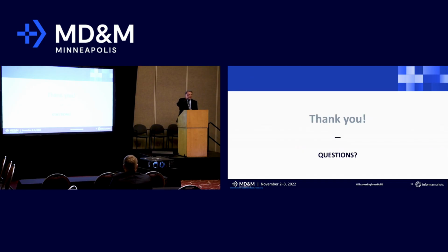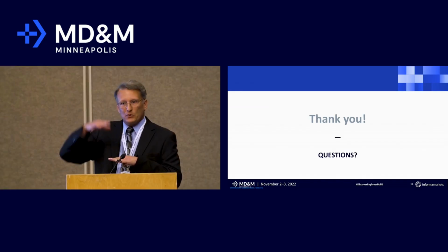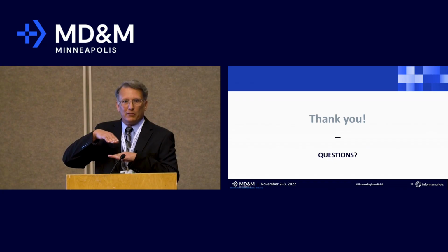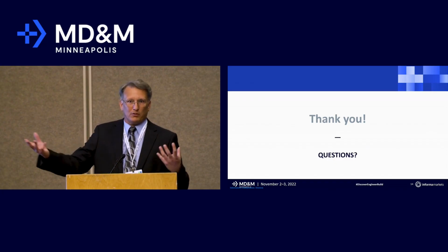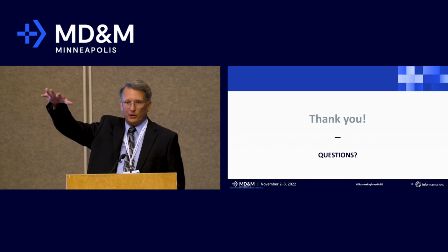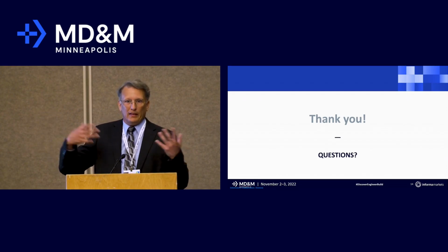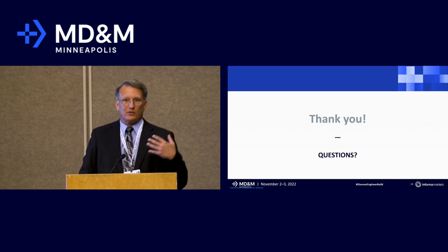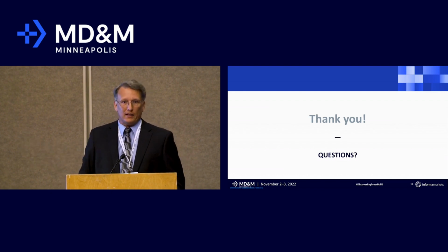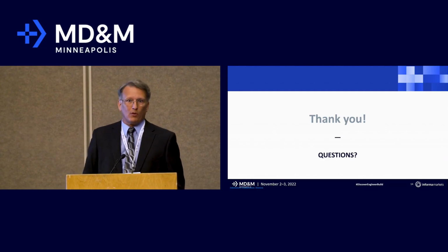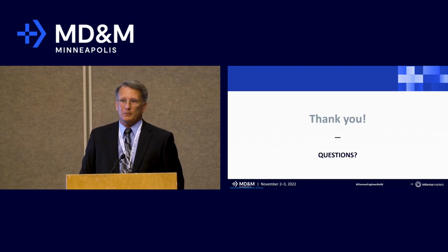The definition of residual risk? Yeah, residual risk is, and I talked a little bit about it last year, but risk really can never go to complete zero. So there's always some level of risk, some level of uncertainty that remains. Residual is just leftover risk. Once you've done all your product development and process development, what's left over risk-wise? And then the discussion is, is the benefit of your device with those features worth that leftover residual risk?